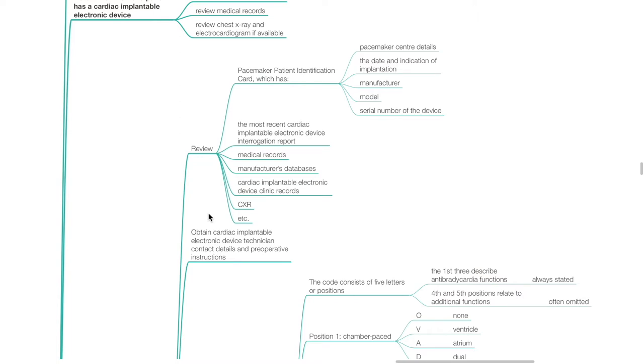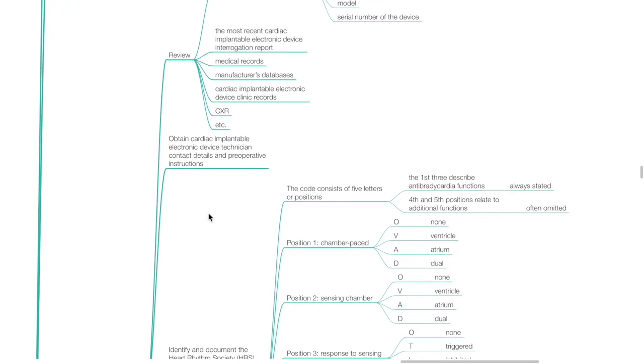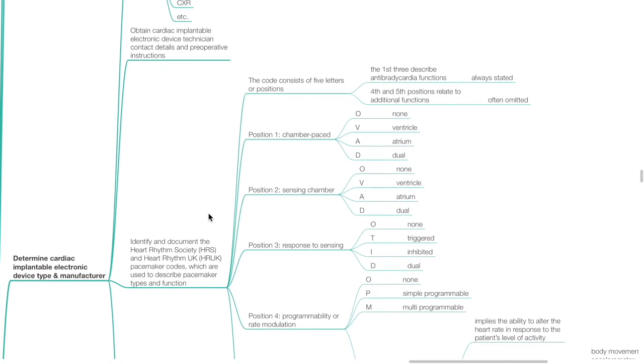Obtain cardiac implantable electronic device technician contact details and preoperative instructions. Identify and document the Heart Rhythm Society and Heart Rhythm UK pacemaker codes, which are used to describe pacemaker type and function. The code consists of five letters or positions. The first three describe anti-bradycardia functions which are always stated; the fourth and fifth positions relate to additional functions which may be omitted.